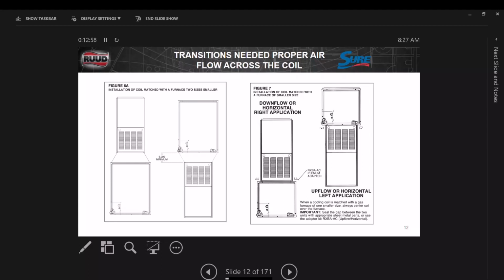I mean, I've done it many a times. I get a call, man, I put this unit in, it's running low pressures. I said, just take me a picture of the install, and they'll send it to me. And I'll see that furnace with the coil straight shot all the way, and this much hanging over the top. That means that much air is not getting to that coil. So that's going to cause us to freeze the coil or run low superheat, subcool, stuff like that. So we say minimum of 6 inches. You can go as high as you like.